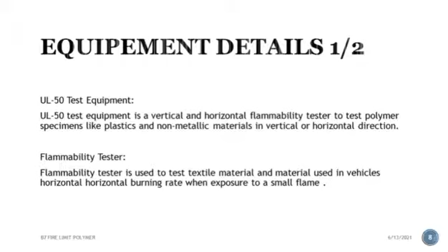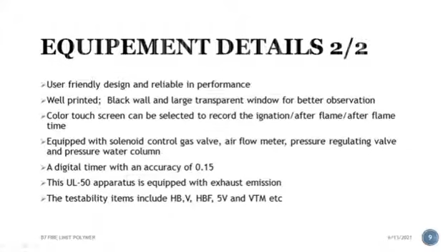Moving on in the equipment details, it is user-friendly and reliable in performance. It is well designed, with a large transparent window for better observation and a black wall. A color touch screen can be used to record the ignition when something starts burning. It is also equipped with a solenoid control gas valve, airflow meter, pressure regulating valve, and pressure water column. A digital timer with an accuracy of 0.1 seconds is also used. This UL50 apparatus is equipped with exhaust emission, meaning a substance is emitted into the atmosphere. The testability items also include HB, V, HBF, 5V, VTM, etc.